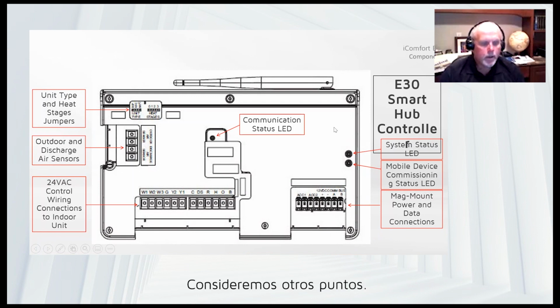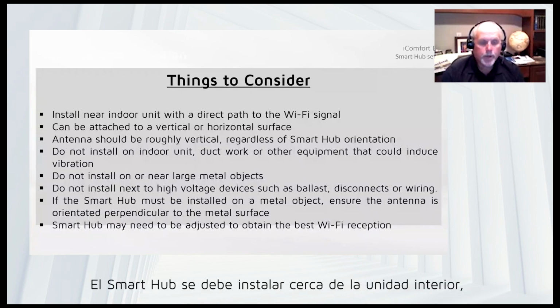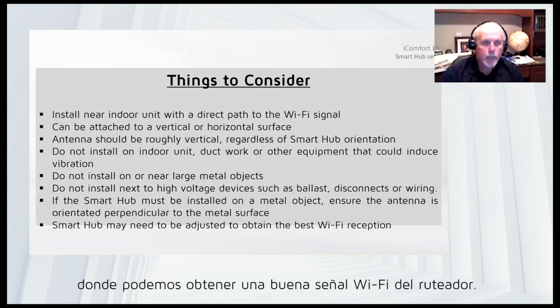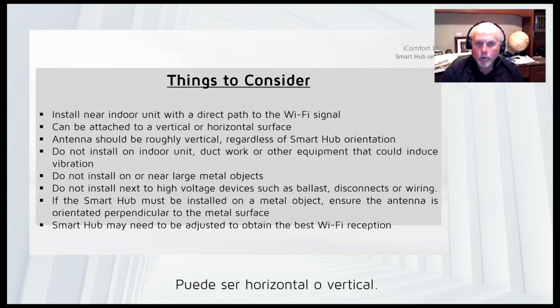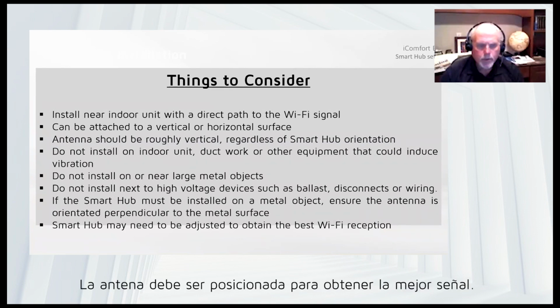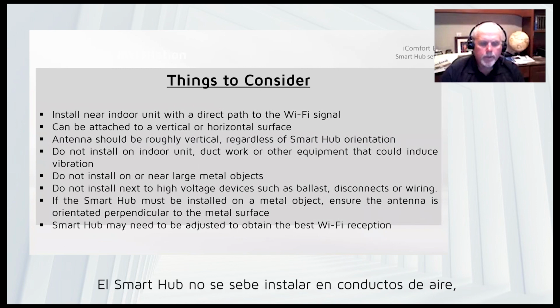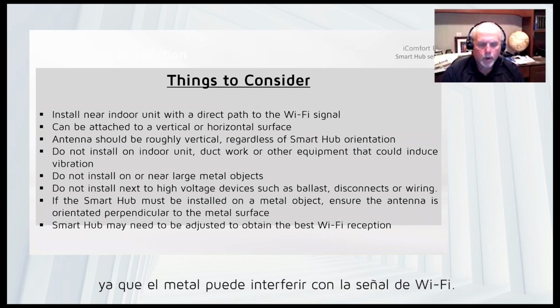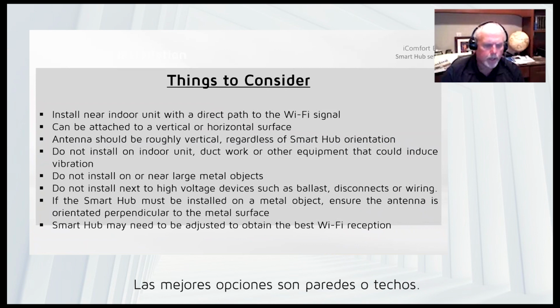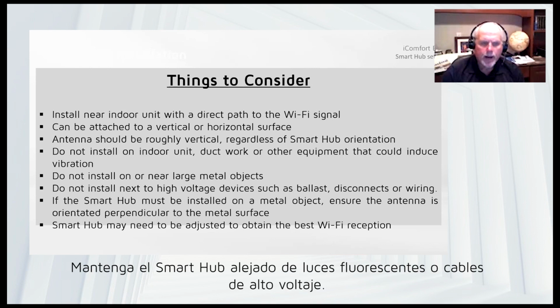So, some things to consider. Install the Smart Hub near the indoor unit, but also where we can get a good Wi-Fi signal from the router. It can be horizontal or vertical, doesn't matter. Either way you want to do that. The antenna, of course, should be out where it can get the best signal. Don't install on the ductwork. Ductwork is metallic and it can interfere with the Wi-Fi signal, so try to not do that. Put it on the wall or maybe on a ceiling joist or something like that. And stay away from fluorescent lights or any other high voltage lines and things like that. Install it where it's not close to those things.